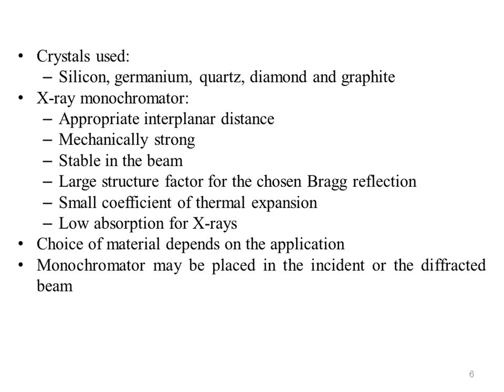For any material used as an X-ray monochromator, the following properties are desirable: forms large good quality crystals with an appropriate interplanar distance, mechanically strong and reasonably easy to cut, stable in the beam, large structure factor for the chosen Bragg reflection, small coefficient of thermal expansion, low absorption for X-rays.